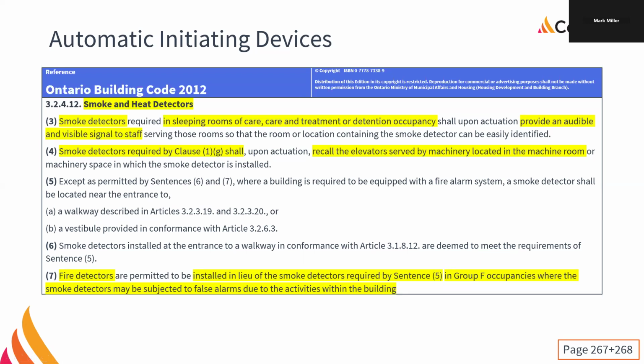So we are going to recall the elevators. Again, we're going to use a relay base. If the smoke detector in the elevator machine room activates, it's going to send a signal to the elevator controller, and it's going to shut down.